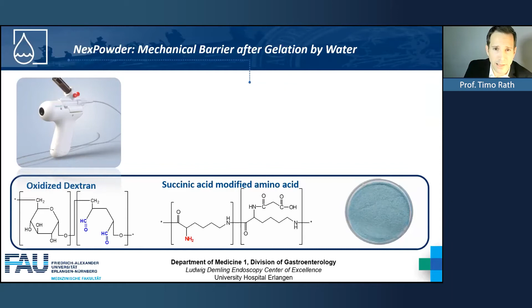So the way you want to use NexPowder, and this is really important, is the following. When you open the box and take the NexPowder, the application device, the spray body out of the package, you want to make sure that the valve is actually closed here in this down position. And ensuring that, you can release here the battery protector and then switch on the device with the power button. And when you do that, you have constant airflow through the spraying catheter.